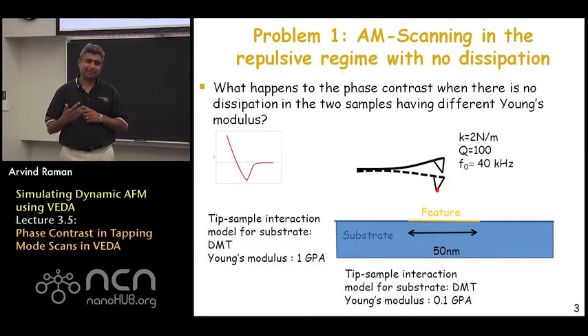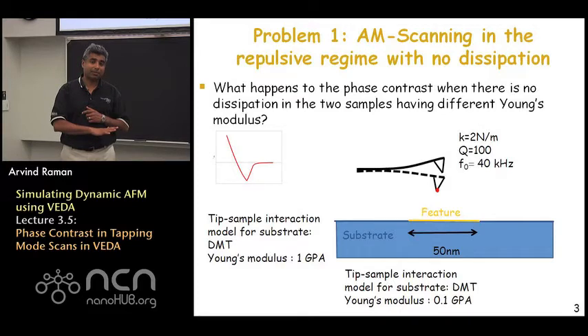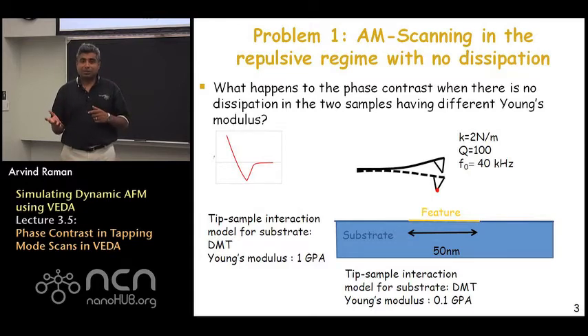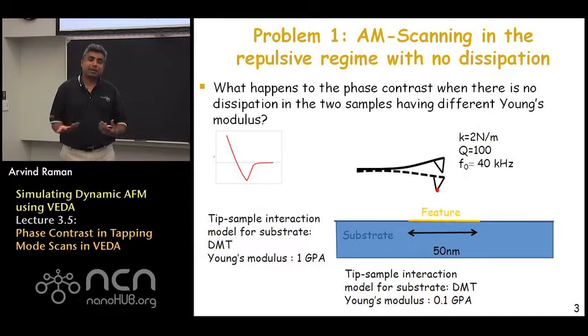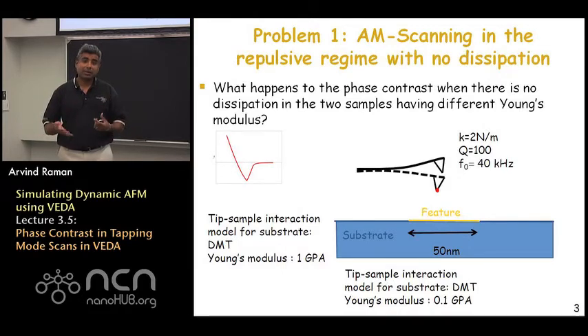We also talked about the fact that you could have situations where you choose a set point where over part of the sample you are in the attractive regime and part in the repulsive regime. In those cases you would get an image where the phase lag is sometimes greater than ninety degrees in some parts and less than ninety degrees in other parts. That tells you it is very hard to compare what is happening in terms of energy dissipation, because one part corresponds to attractive and another to repulsive.